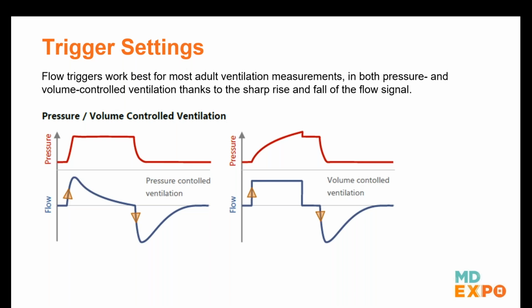Another nice thing here is that it all happens around the zero line. So no matter what pressure we have set up on the ventilator or what volume, usually it just starts at zero flow and then it rises up. In an inspiratory phase and in an exhalation phase, it transitions to negative flow through the analyzer, and then it comes back to zero. So that means our trigger settings are not dependent on the settings on the ventilator.